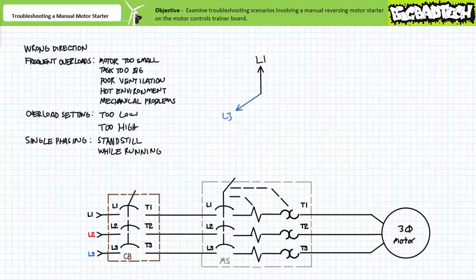If however, one horse leaves or exerts significantly less force than the other two, the balance condition is upset and things go downhill in a hurry. Single phasing results in the loss phase supplying no current, yet the two remaining phases supply more. More current means the motor overloads quicker.